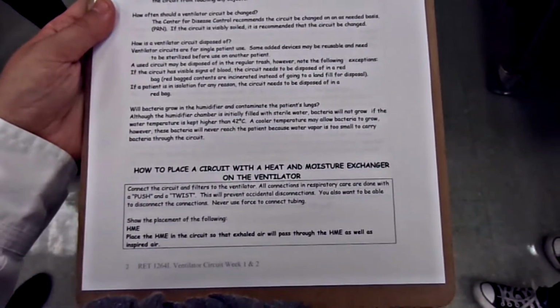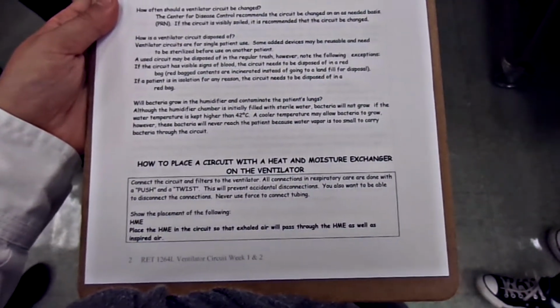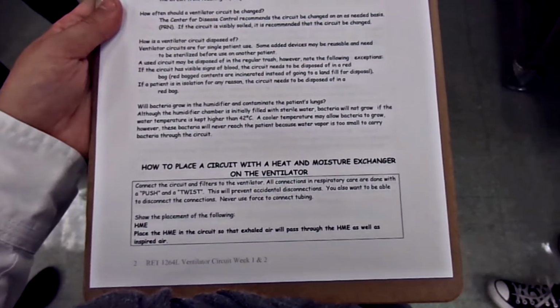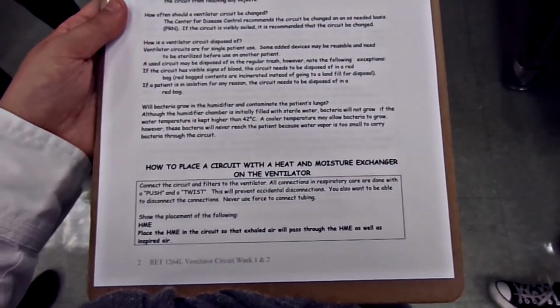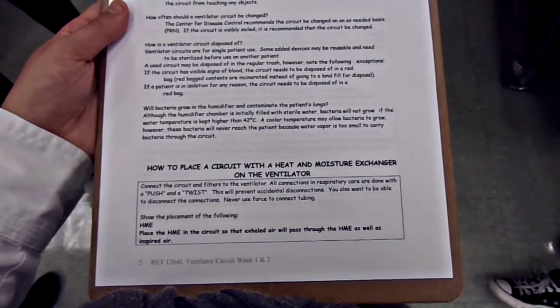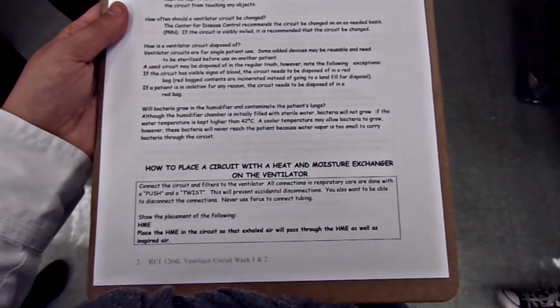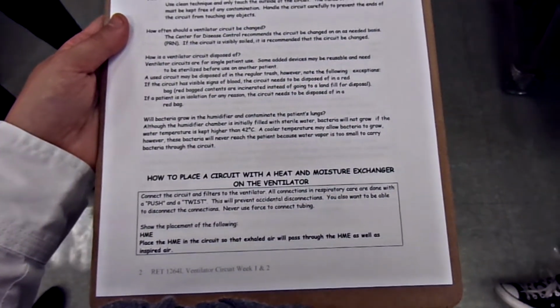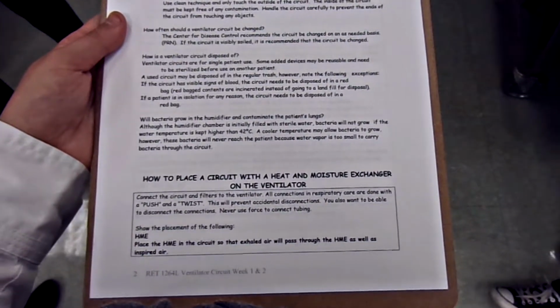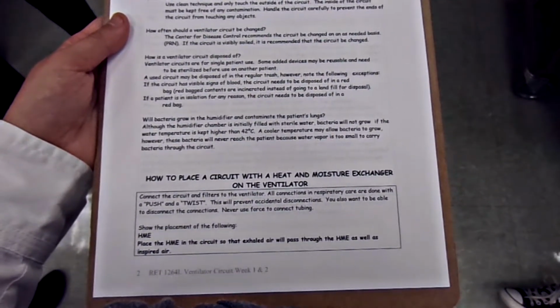How to place a circuit with a heat and moisture exchanger on the ventilator. Connect the circuit and filters to the ventilator. All connections in respiratory care are done with a push and a twist. This will prevent accidental disconnections. You also want to be able to disconnect the connections. Never use force when connecting tubing.